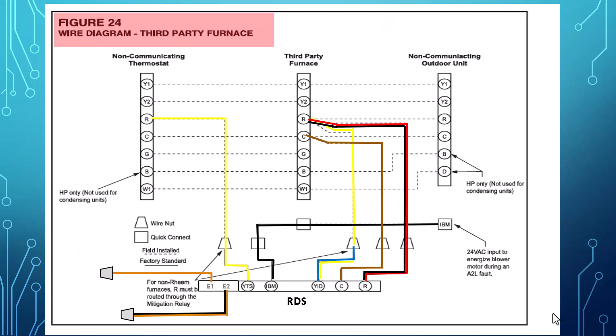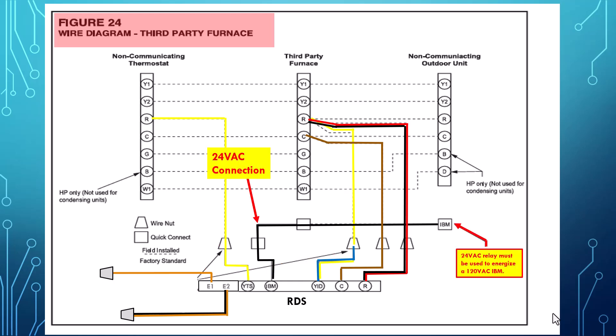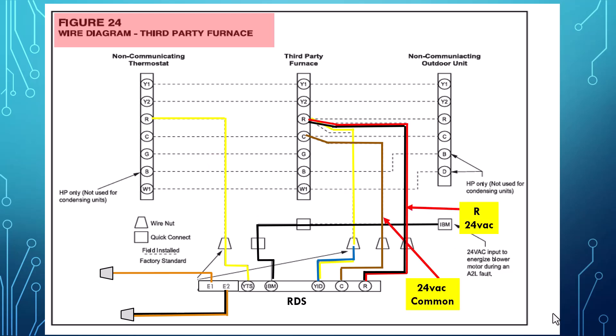Now let's look at a third party furnace wire up — this would be a non-Rheem type furnace. We have our yellow from the RDS going directly to R on the non-communicating thermostat, and we have our yellow and blue going from the RDS directly to R on the furnace. The indoor blower connection from the RDS to the furnace is a 24 volt connection designed to work with ECM type motors. If you're using a 120 volt motor, you'll need a relay at this point to operate the blower. Then we'll hook up our 24 volt R, which is the black and red wire, directly from the RDS to the furnace, and our brown wire 24 volt common to the furnace common. We're not using the orange and orange and black wires in this application.